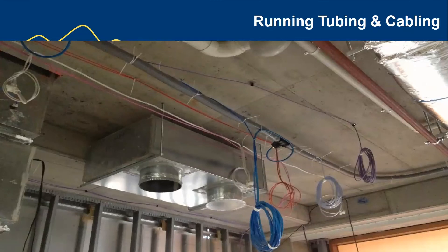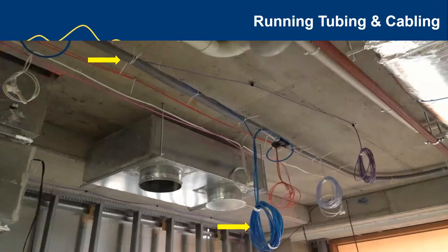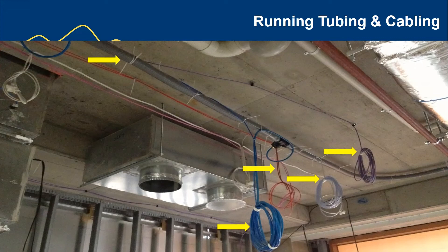Here we see a ceiling location with a ring vacuum. This is the ring vacuum for remote particle counters and air samplers that will pull vacuum from a centralized vacuum system. There is a vacuum line tapped off from the ring vacuum. We've also got DP lines here, which are separate to the ring vacuum — these are for differential pressure sensors. And we have Ethernet connections for other sensors that will also pair up and communicate with particle counters, temperature-humidity sensors, and DP sensors. In this particular project, we decided to colour-code the Ethernet connections so we knew straight away which color was for which particular particle counter, temperature-humidity sensor, or DP sensor.